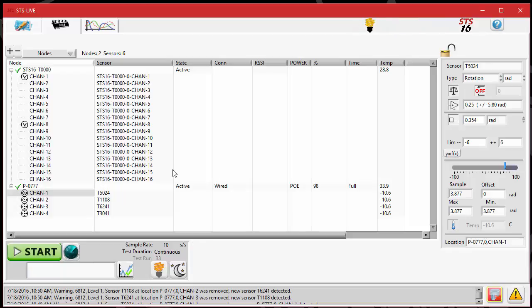So you may notice that when you're running a sensor scan, or at other times when you're using live, that there's some information that pops up here in the bottom field of STS-LIVE. So if you read this, this is a warning, and it's just telling you that there's a sensor change that has been made. So the sensor T1108 at the location, which is the channel, was removed, and this new sensor was detected, and that happened because I switched those 2 gauges.